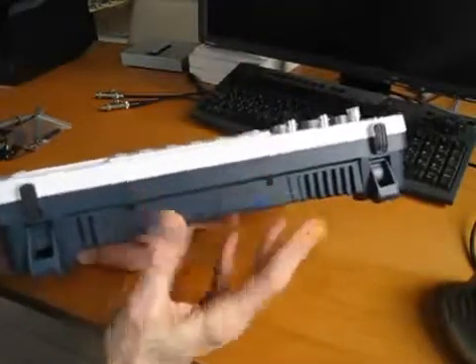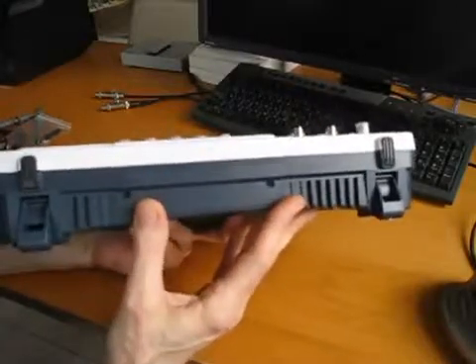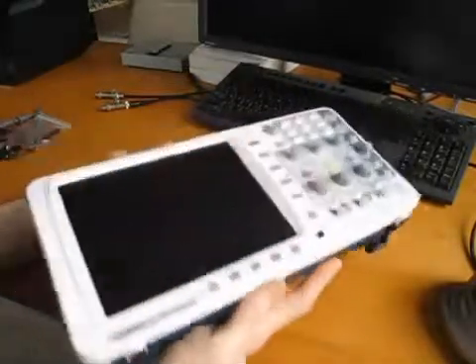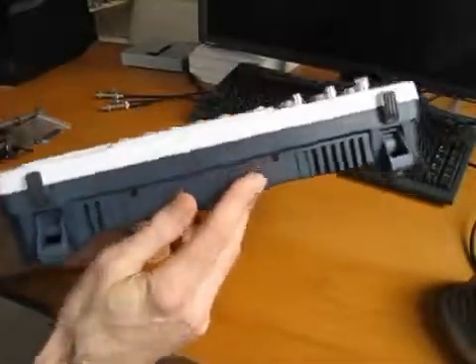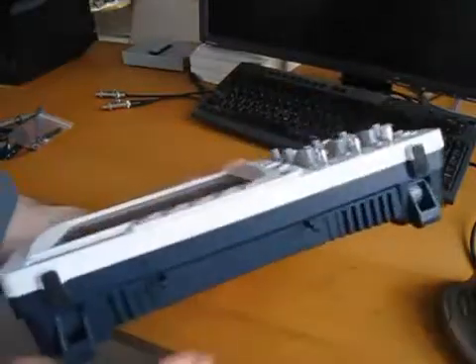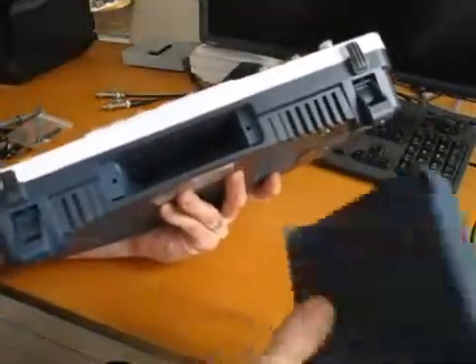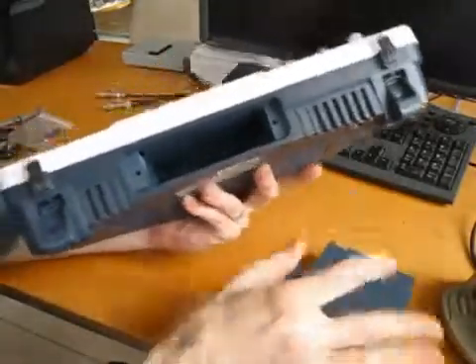So clearly, if you do have a battery, sometimes you want to use it and sometimes you don't. If you're going to an on-site job where there's plenty of AC available and you don't have to worry about the battery, you might want to leave it out just to leave out the weight of carrying it. But the battery compartment itself is attached with very long screws. So here's the battery compartment with the screws loosened and the block being taken out. This obviously is just a kind of insert when there's no battery there. Battery does not go inside it.